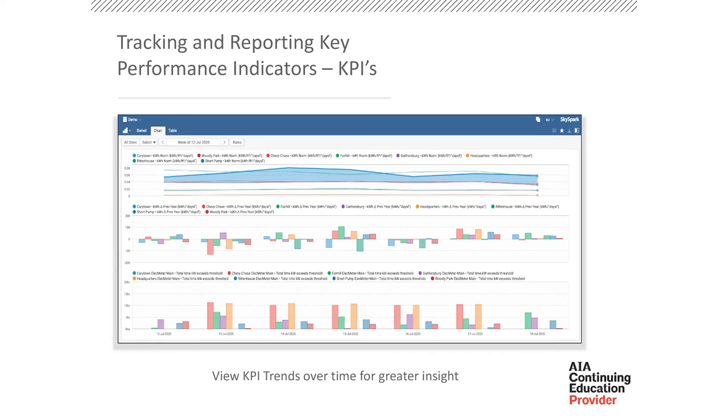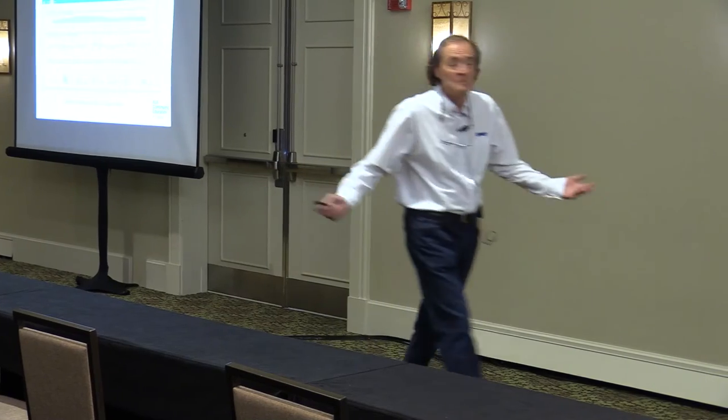Same thing with KPIs. Hey, all my KPIs look good today. Yeah, they do, but here's your trend. This is one of the best things we can do with KPIs, is to trend them. They might be a line trend, or that middle one is a delta trend, where the baseline is the zero line, and we're seeing on a time basis, day by day, site by site, those different colors, whether they're above or below our baseline goal. Or it might be cumulative, like hours of runtime, operation, total kWh, et cetera. So that's the insight we really get from KPIs, seeing what they're doing over time.